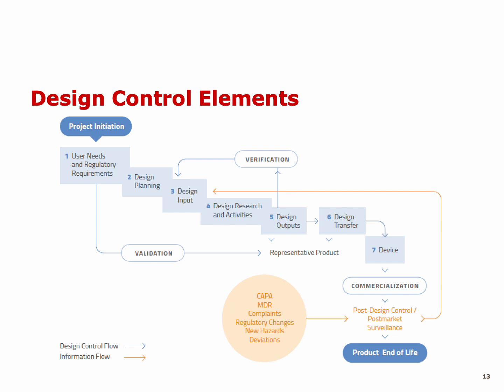Here, when we talk about post-market surveillance, we do have to report any safety issue experienced by our users of medical devices to the regulatory authorities, not only in the one country in which the issue occurred, but in any country where we are selling the same medical device. And now, for example, in Canada, if there's any untoward medical occurrence experienced by a patient using our medical device, we'll need to produce what we call mandatory reporting.